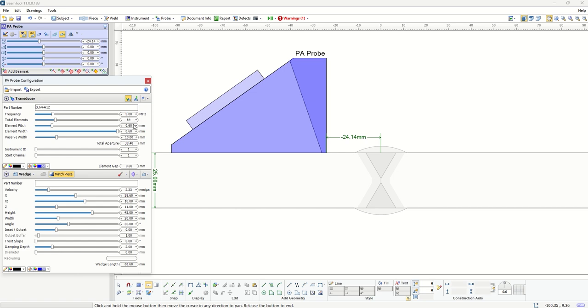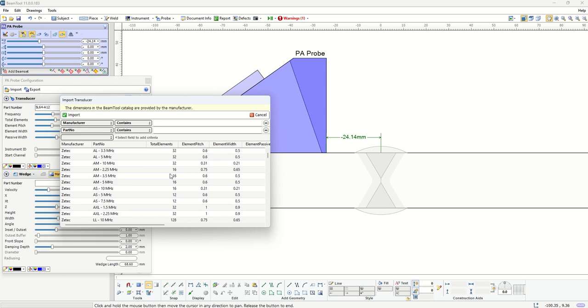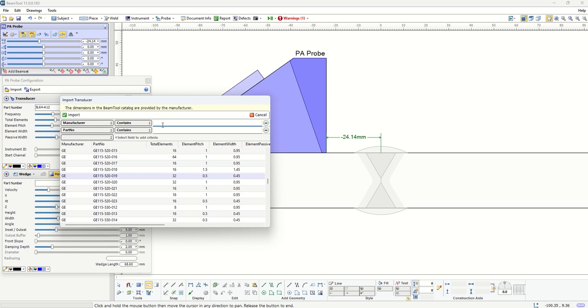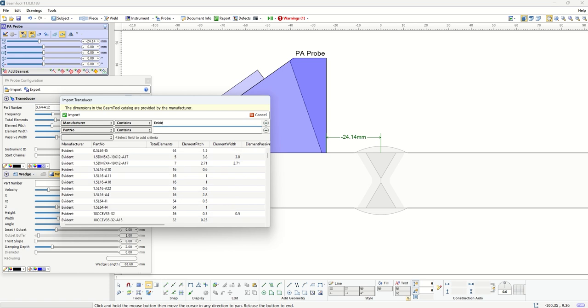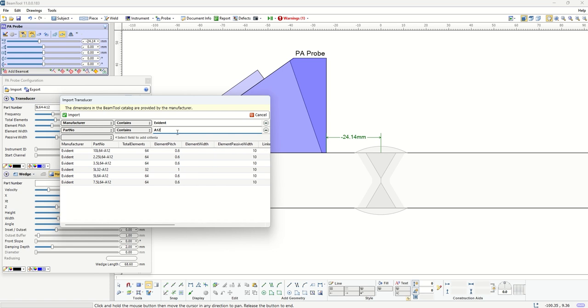Since I've used this probe before, you'll notice I have it saved in my workspace. If you're using a custom probe, you can always define the parameters directly here, or you can import from the catalog, where most common probes from different manufacturers are listed. For instance, for the same probe I just showed, I can choose the manufacturer Evident and enter a part number like A12, and you'll see all the matching probes appear—5L64A12 is the one I actually use here.